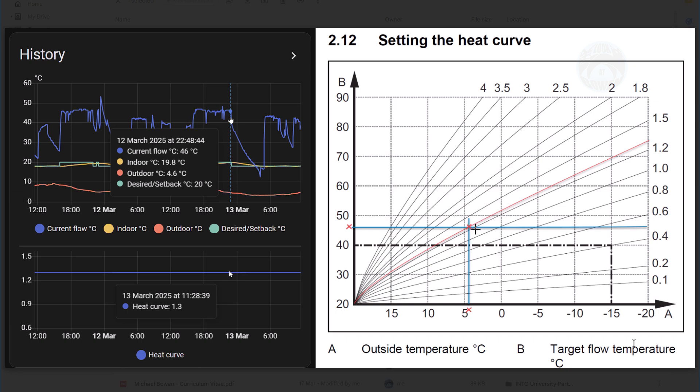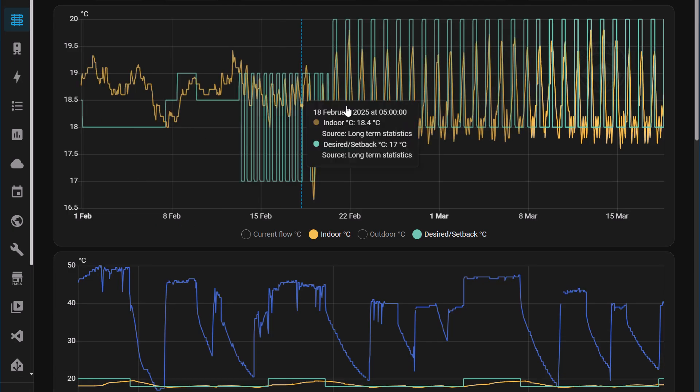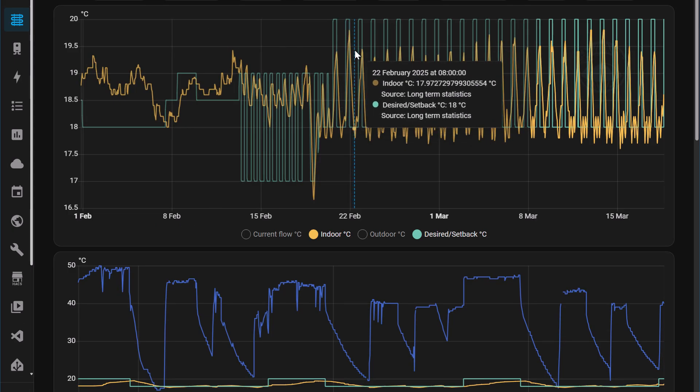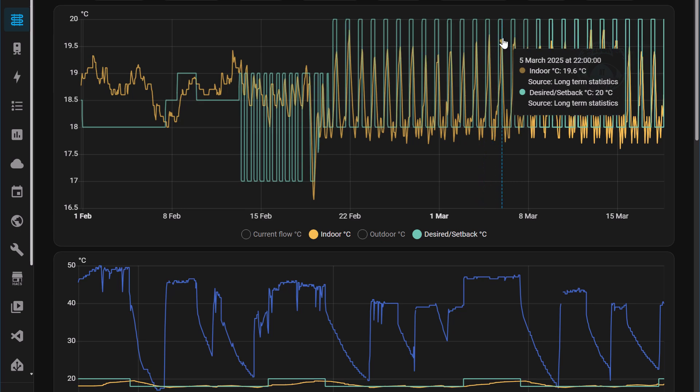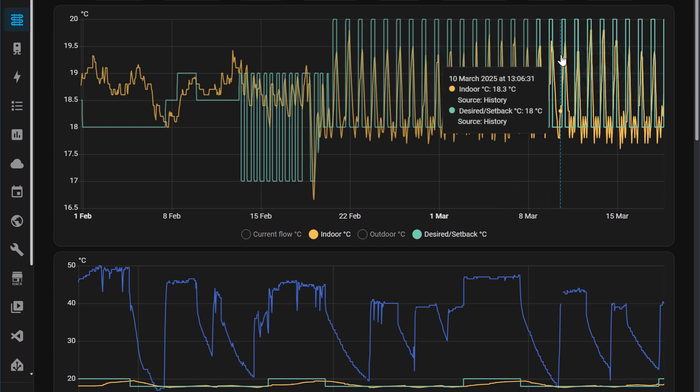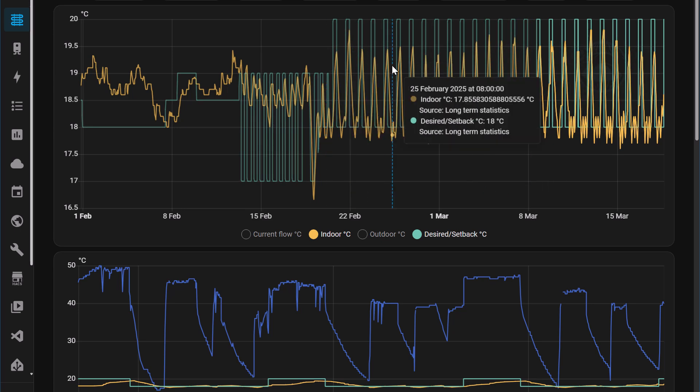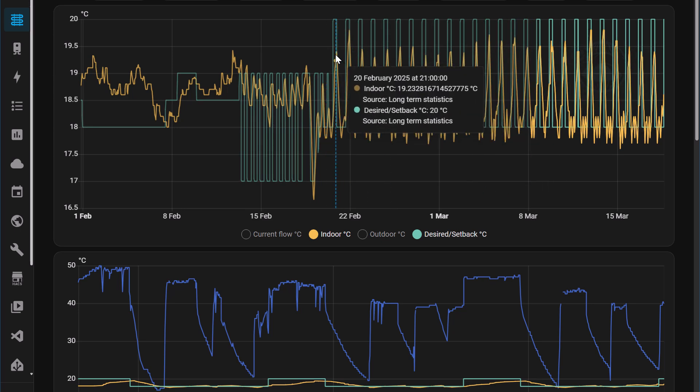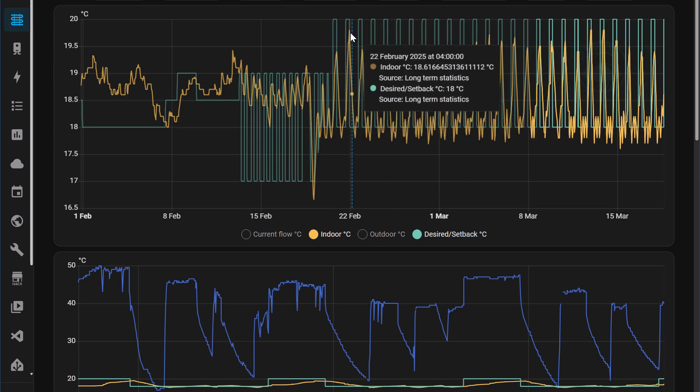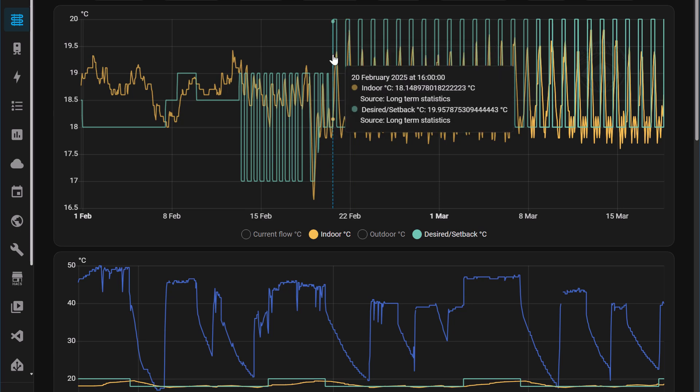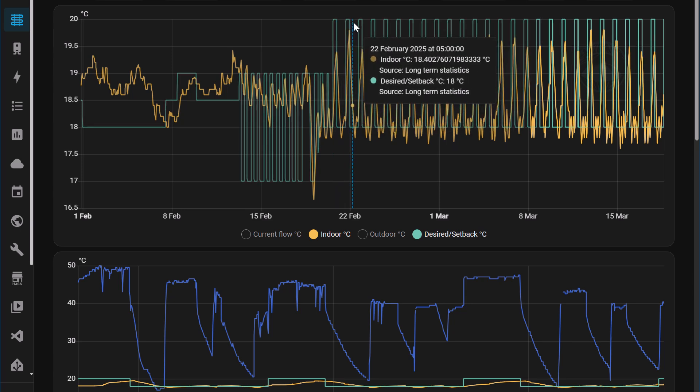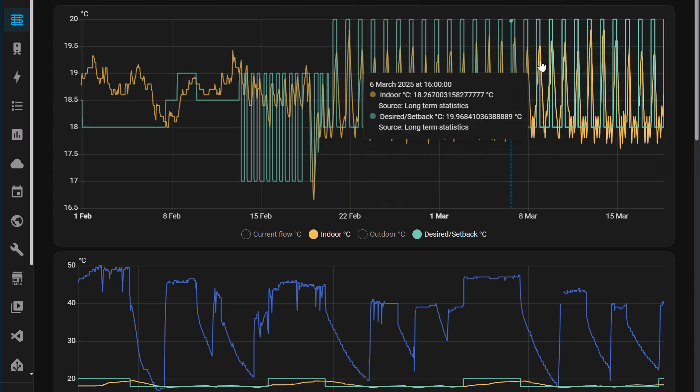I wouldn't want to lower it. And I certainly wouldn't want to increase it because I'm pretty sure if I increase it to 1.4, I will reach the desired temperature of 20. And the indoor temperature will be around about 20. And as I said, I'm not really keen on a 20 degree indoor temperature. I'm happy with the 19.5. So that slight negative is that the heat curve that I'm on is obviously not the right one, but it's actually perfect for this setup.